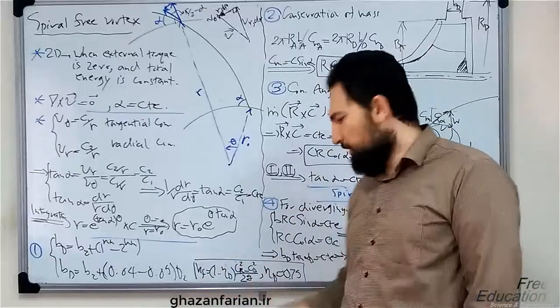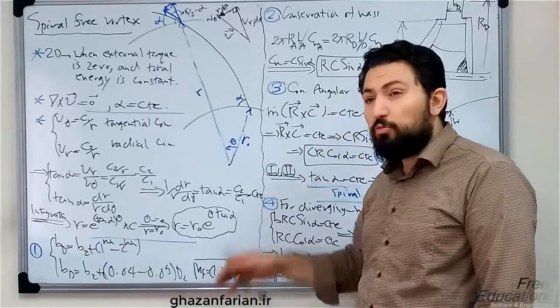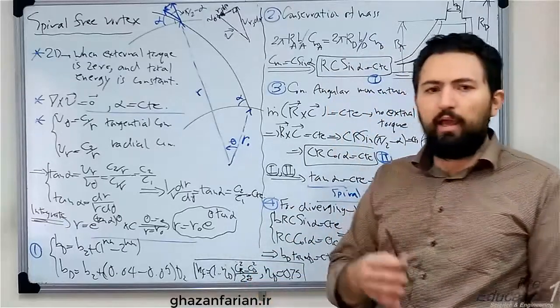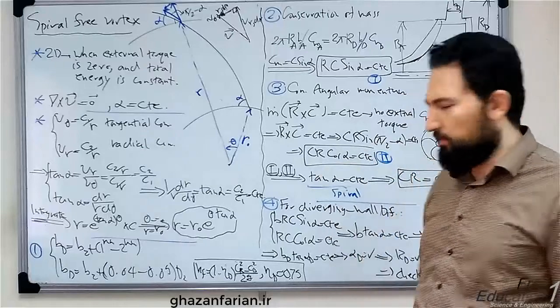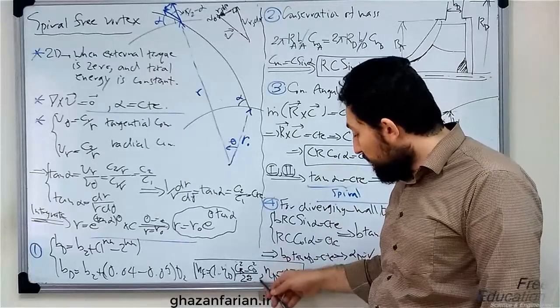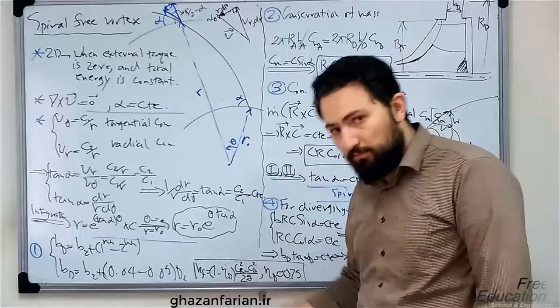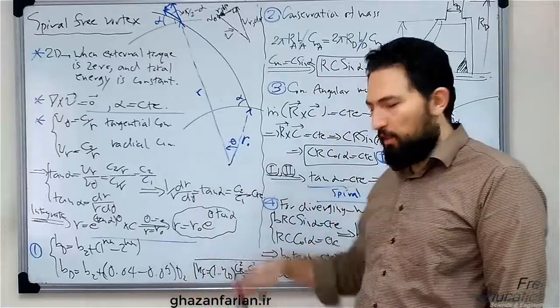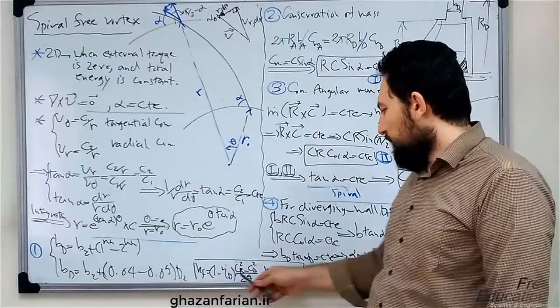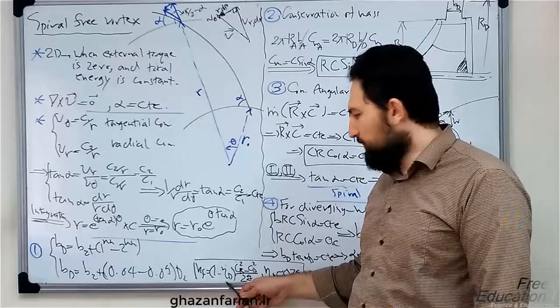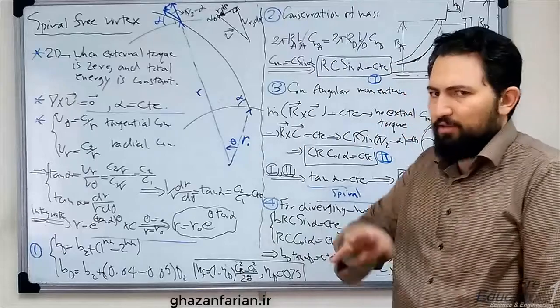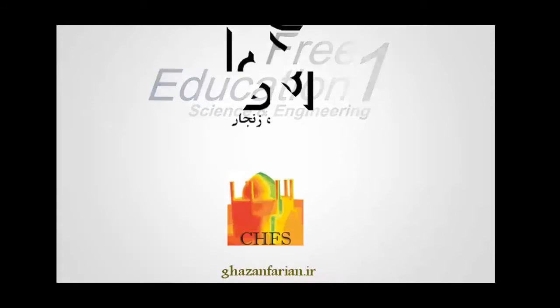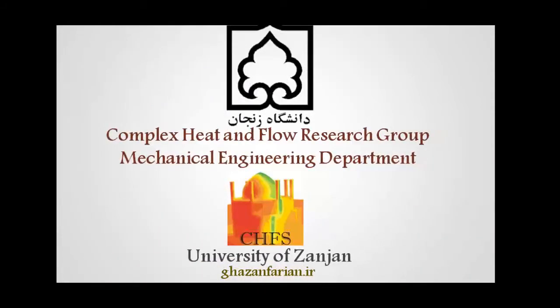If you substitute this suggestion into the relation, you find that the hydraulic loss is approximately equal to one-fourth of the kinetic energy head difference inside the diffuser. This means that if you decrease the magnitude of the velocity at the outlet of the diffuser, the frictional and hydraulic losses will increase. If the efficiency of the diffuser is 100%, the losses are zero, which is not a realistic case of course.